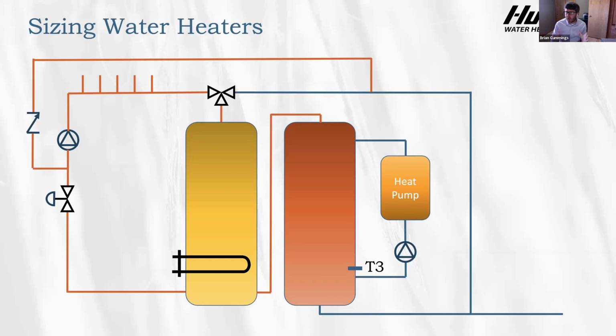However, you have all this pressure in all these other tanks that's pushing on this small tank at the end of your system. And to not make this ASME rated seems a little bit odd to me. It's like an expansion tank for a system like this. It doesn't meet either of those criteria, but most of the time it's going to be specified ASME because there are larger tanks. There are things within the system that are providing the pressure that could be an issue for it. So I would strongly recommend, and when we do these type of systems, that you have this tank be ASME rated and the fittings be designed properly for the flow rates and stuff in the system.